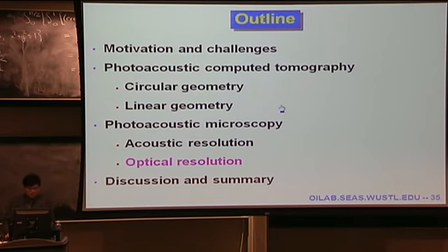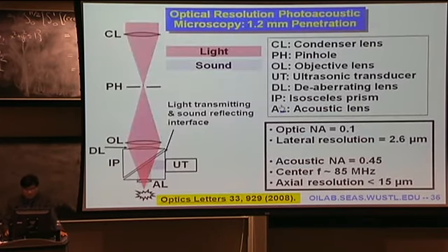Photoacoustic microscopy also comes in optical resolution, where we're back within 1 millimeter penetration capability. In fact, this particular device penetrates about 1.2 millimeters in the skin. So within this 1 millimeter range, you can focus light. So photons are not fully scattered, fully diffused yet. There are still some photons that are ballistic or quasi-ballistic, meaning they travel relatively straight toward the target region.